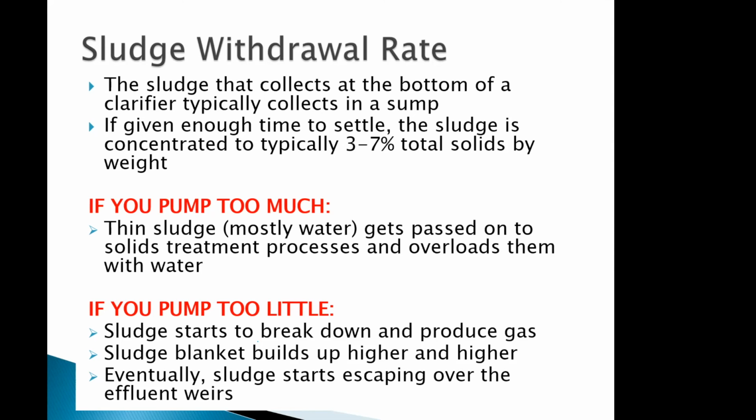So we could just turn on a pump full blast and just let it pump out of that sump all the time. Anytime any bit of solids gets into that sump, it gets pumped out, right? That's one approach. But here's the problem. If we end up pumping too much, we're not going to be pumping many solids. We'll be mostly pumping water because we're not allowing the solids enough time to concentrate. Now, pumping water isn't necessarily bad, but if we're sending the sludge onto a solids treatment process, such as a dewatering process or a digester process, we would really prefer just to have the solids and less water. So pumping water is usually bad for our downstream solids treatment process, okay?